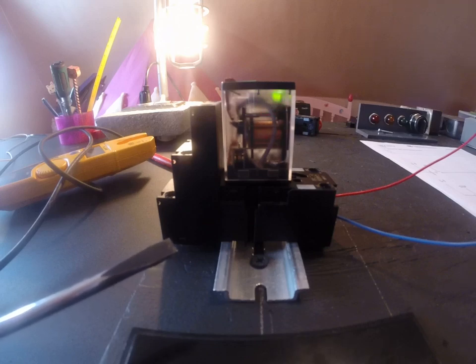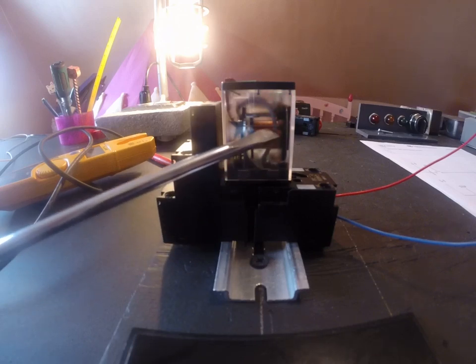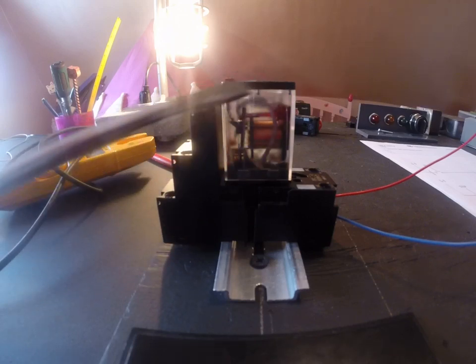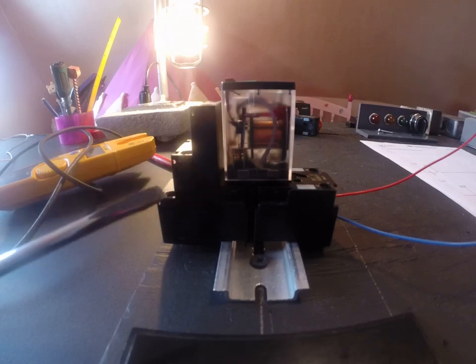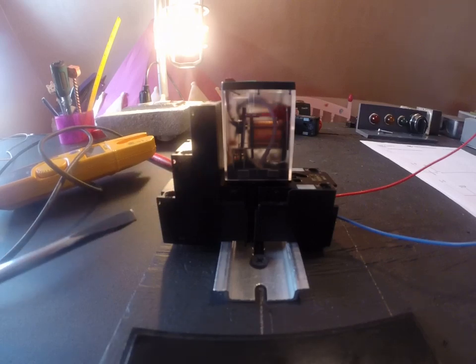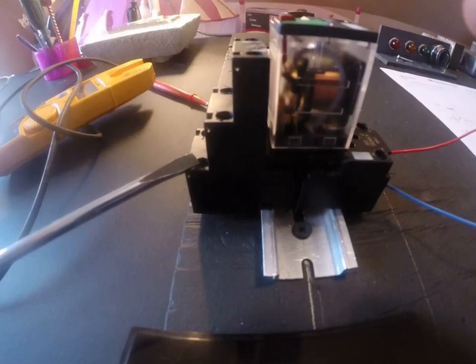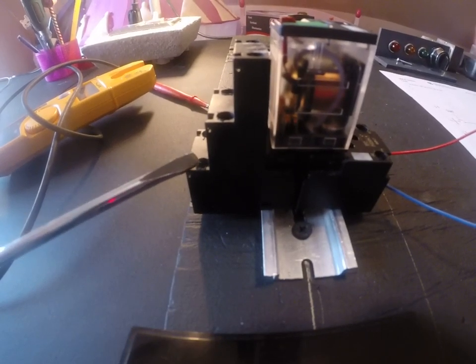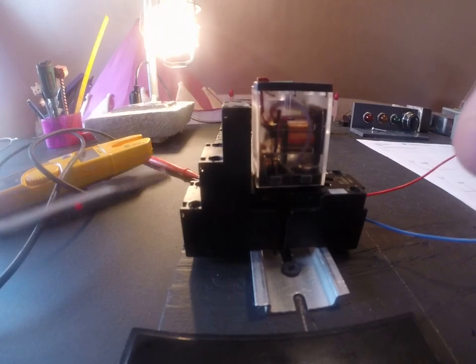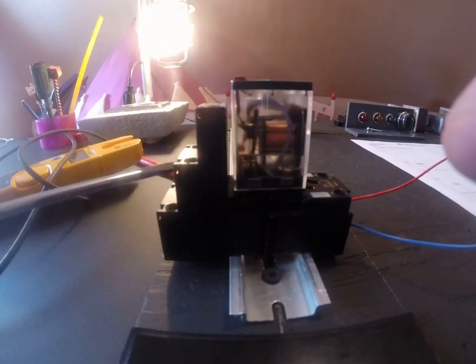So what's happening is this white wire is actually connected to my common terminal. The common terminal is actually these screws on the lower base. It actually goes common, normally open, normally closed. There's three screws on this side of the relay. An identical setup on the other side.